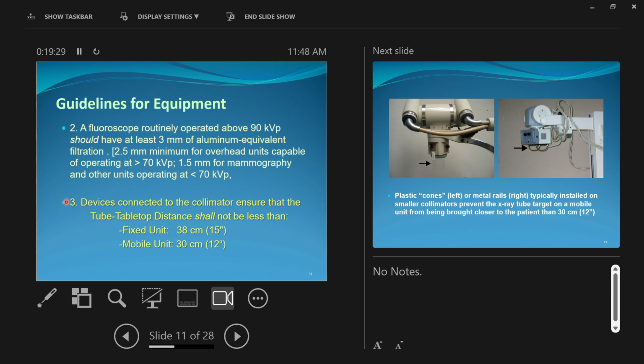There's a minimum distance that our x-ray tubes can get to the tabletops, okay? Your collimator boxes are these big blocky things for a good reason. They prevent you from lowering the x-ray tube to where it touches the patient, right? There's the box in between the patient and the x-ray tube, even if you brought it all the way down to the patient, okay? So the minimum possible distance, 15 inches for fixed units, 12 inches for mobile units.